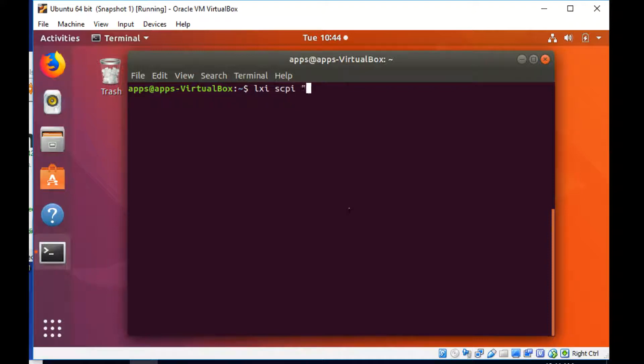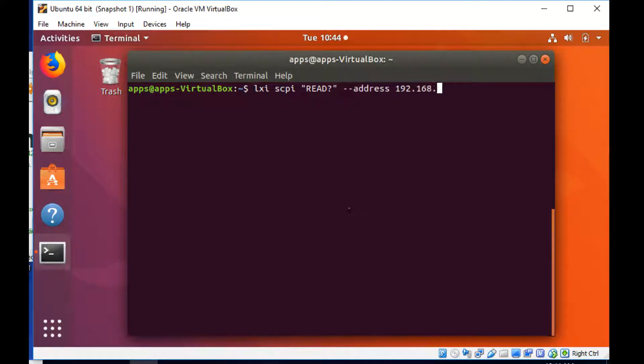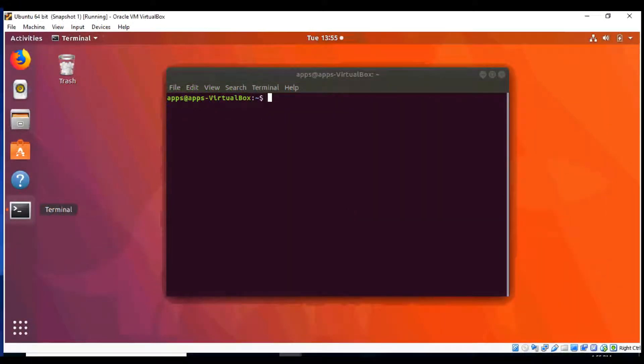This is the LXI SCPI, so we're actually able to send direct commands. We're going to send the read command to the digital multimeter, and it's instantly going to bring back that voltage measurement. So we can actually do remote measurements from a distance from the command line.